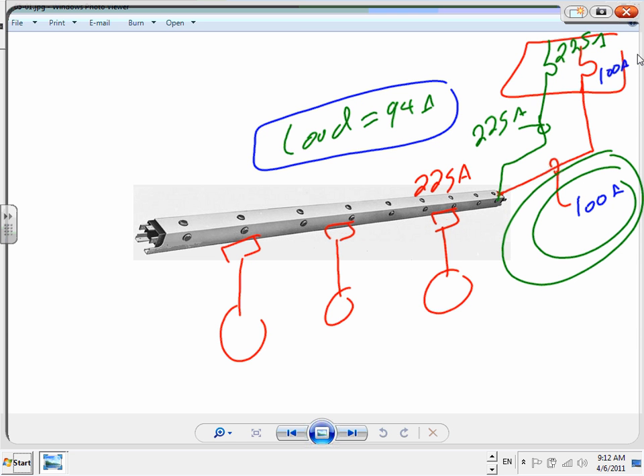As I said, look, had this load been, let's just throw in 201 amps, it would make a lot of sense, guys, to make the cable 225 amp and the overcurrent protection device 225. It all goes by what's the load that's fed from this piece of equipment. And it's really judgment. You can have a load of 94 and decide to use 225, 225, 225. That's okay. But you can save the customer some money, and some can argue, well, what if they add load in the future? Personally, if the difference is twice like this, I wouldn't hesitate. Like this one, 94 amp, and the next is 225. That's double. I wouldn't hesitate to size based on the load.